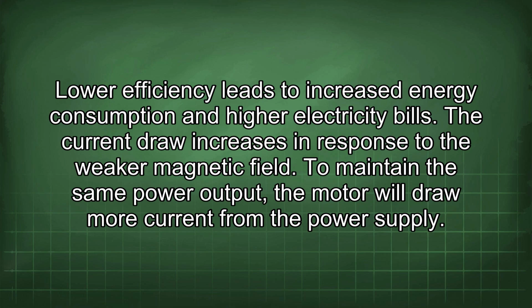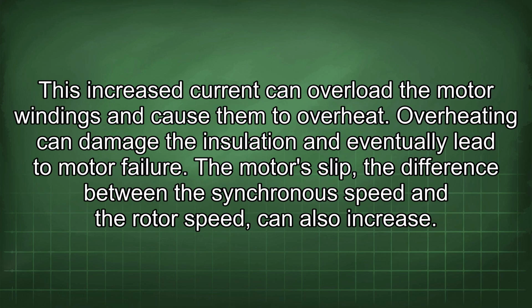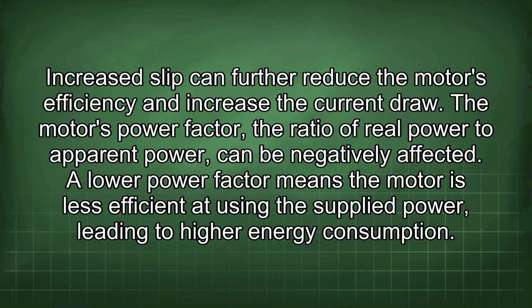The current draw increases in response to the weaker magnetic field. To maintain the same power output, the motor will draw more current from the power supply. This increased current can overload the motor windings and cause them to overheat. Overheating can damage the insulation and eventually lead to motor failure. The motor's slip, the difference between the synchronous speed and the rotor speed, can also increase. Increased slip can further reduce the motor's efficiency and increase the current draw.